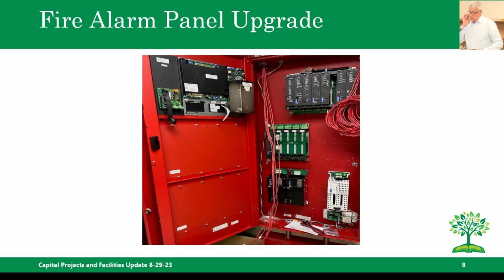In addition to the HVAC equipment, we had a fire alarm panel at the middle school that was at the end of its life expectancy, and it wouldn't support all the new relay points required for this HVAC equipment. Understand, when you have a fan coil or you're pushing air through the building through ducts, you're going to have dampers in those ducts, and in case of a fire, all of those relays have to shut down all this equipment automatically. So this is the new fire alarm panel now at the middle school.